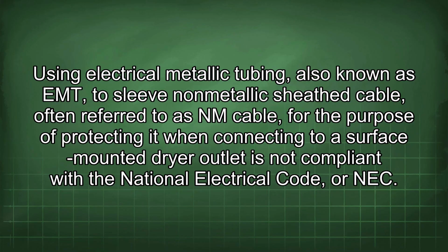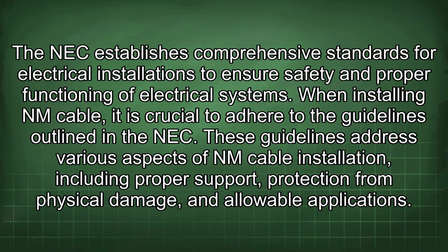Using electrical metallic tubing, also known as EMT, to sleeve non-metallic sheath cable, often referred to as NM cable, for the purpose of protecting it when connecting to a surface-mounted dryer outlet, is not compliant with the National Electrical Code, or NEC. The NEC establishes comprehensive standards for electrical installations to ensure safety and proper functioning of electrical systems. When installing NM cable, it is crucial to adhere to the guidelines outlined in the NEC.